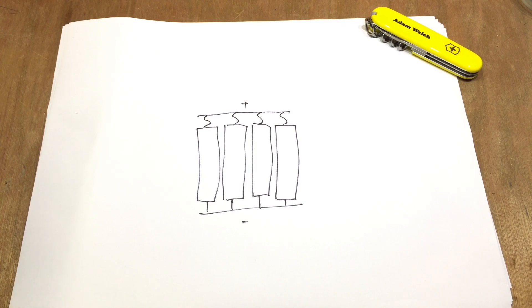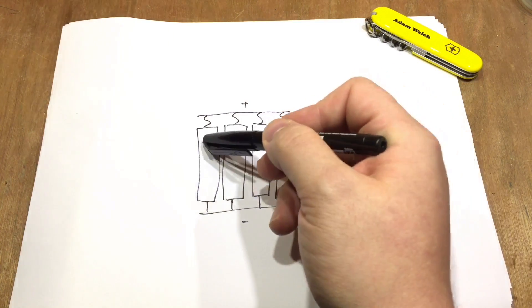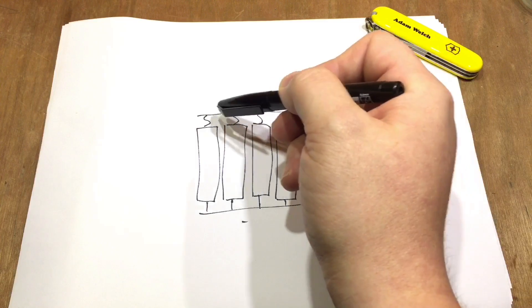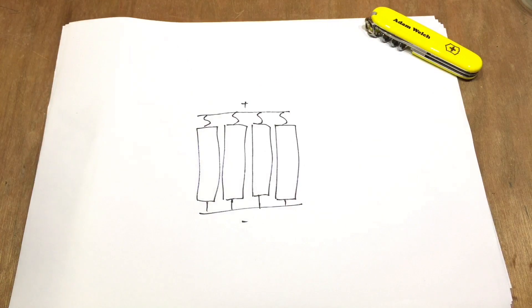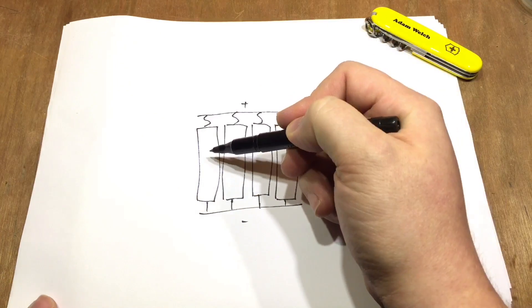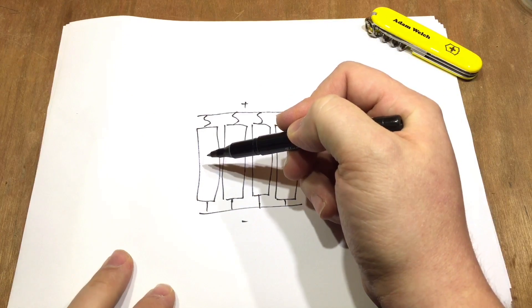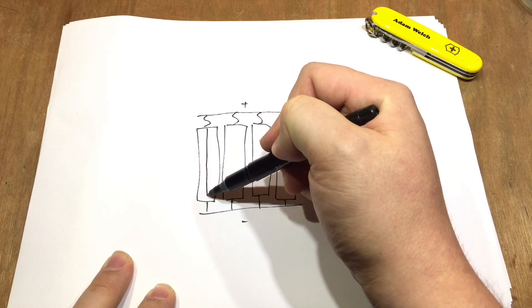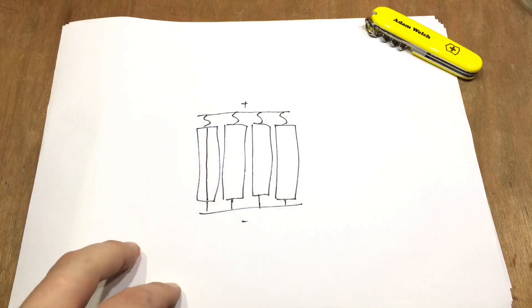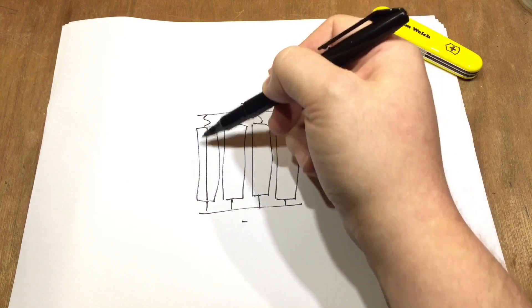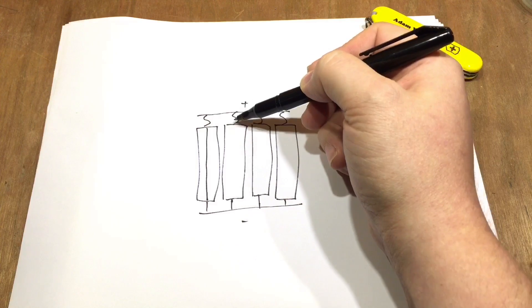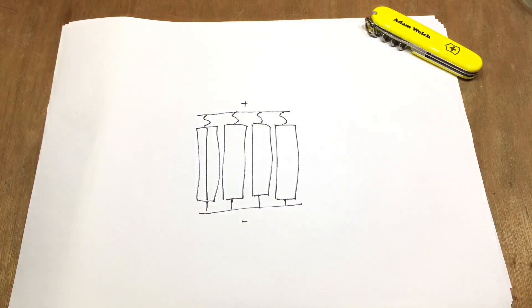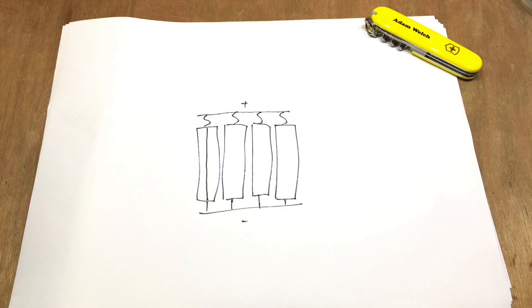Each individual cell has its own individual fuse here at the top. So let's imagine this cell on the left-hand side goes faulty, it goes short circuit. Then the other cells have a short circuit as well, so their positive is connected to their negative.